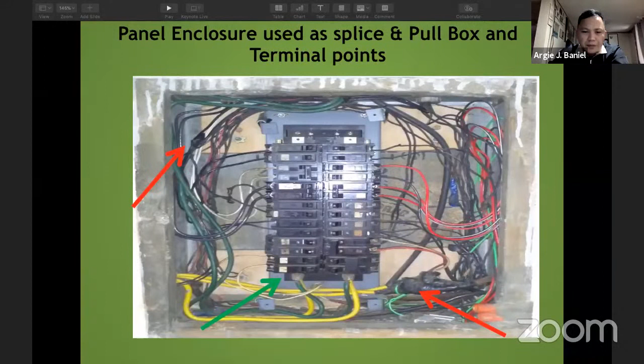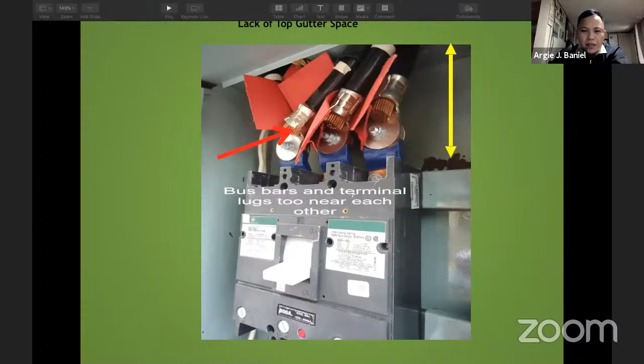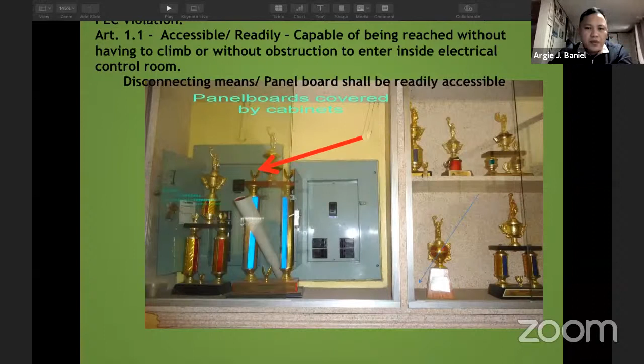So the panel enclosure is used as splice and pull boxes and terminal points. Bus bars and terminal lugs are too near each other, they almost touch. Panel boards covered by cabinets. This is a PEC violation, because the panel board shall be accessible, readily and capable of being reached without having to climb, and without obstruction to enter inside the electrical room. Disconnecting means, panel board shall be readily accessible. So this is a PEC violation.